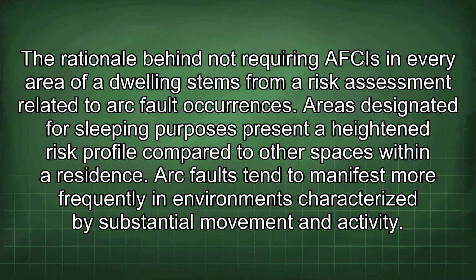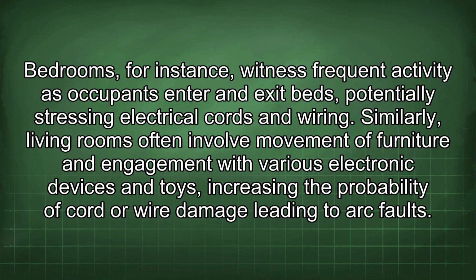to arc fault occurrences. Areas designated for sleeping purposes present a heightened risk profile compared to other spaces within a residence. Arc faults tend to manifest more frequently in environments characterized by substantial movement and activity. Bedrooms, for instance, witness frequent activity as occupants enter and exit beds, potentially stressing electrical cords and wiring. Similarly, living rooms often involve movement of furniture and engagement with various electronic devices and toys, increasing the probability of cord or wire damage leading to arc faults.